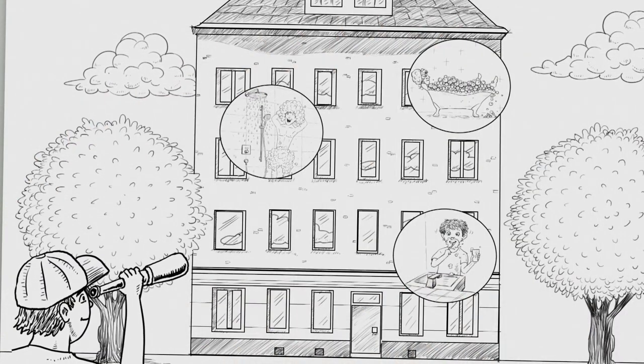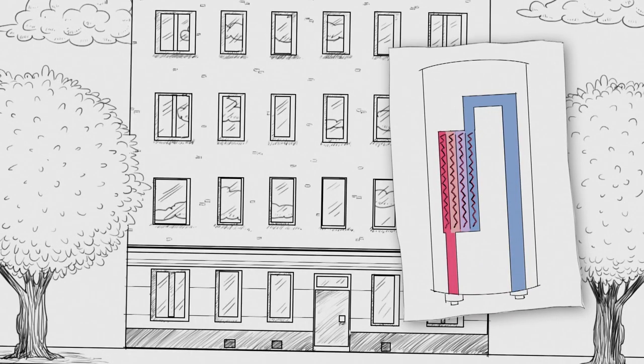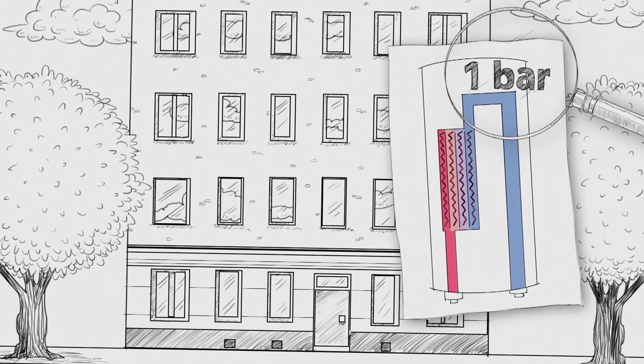The water pressure in the system also plays an important role. For this, we will take a look at the installation room. To function, our appliances need a supply pressure of at least one bar. If this isn't available in your area, a pressure booster station needs to be employed.